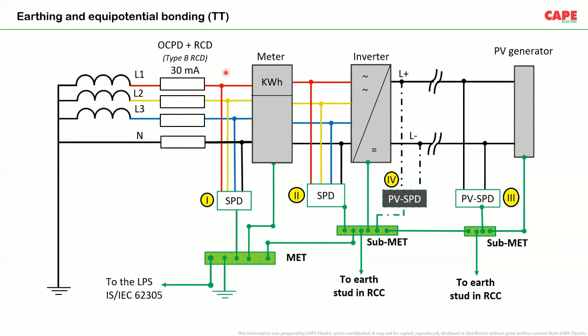This is the connection diagram for a TT system. In a TT system, all the green wires, all these green connections, that means the protective or functional earth connections, are electrically separated from the source earthing. See, on the left side, this is the source earthing. At the consumer premise, the earthing is completely separated. First, the user or the company giving the solar PV connection, or the contractor, has to understand the type of electricity supply from the electricity company, and has to select the appropriate earthing method.